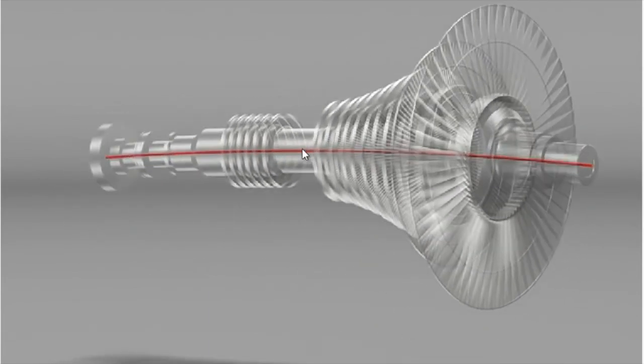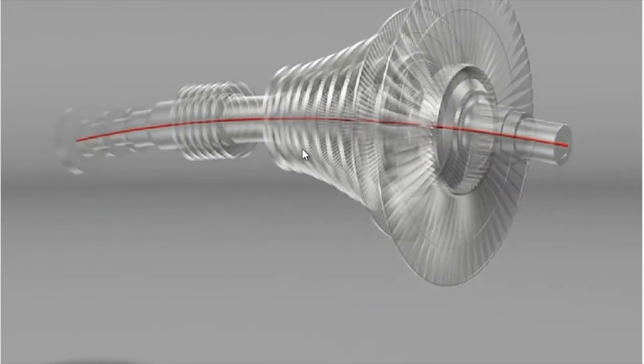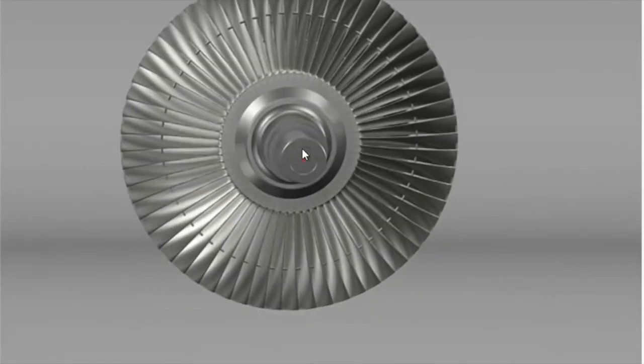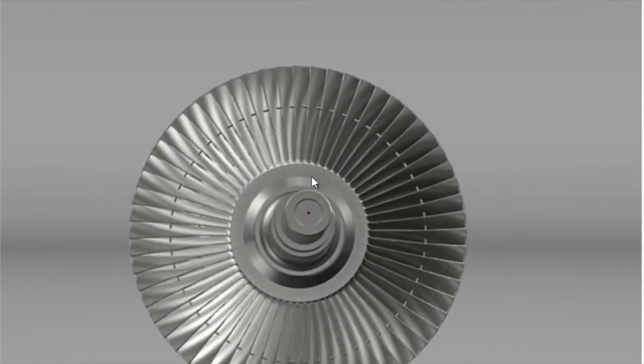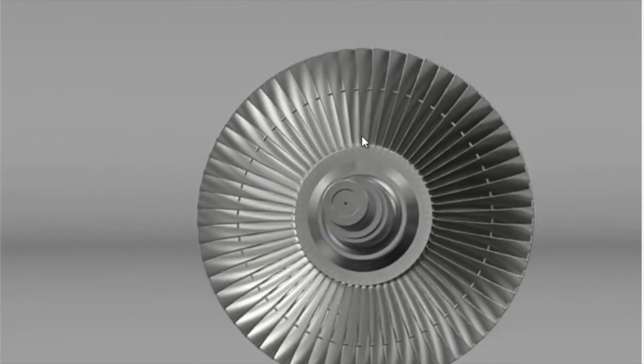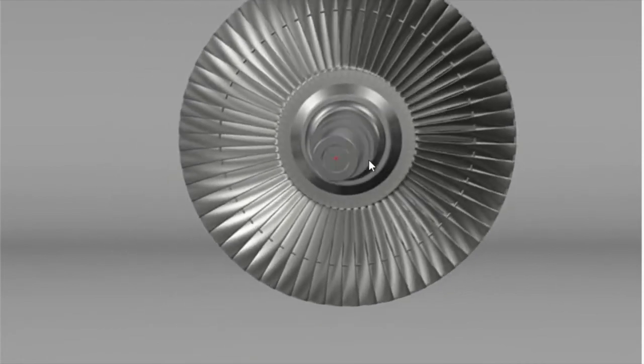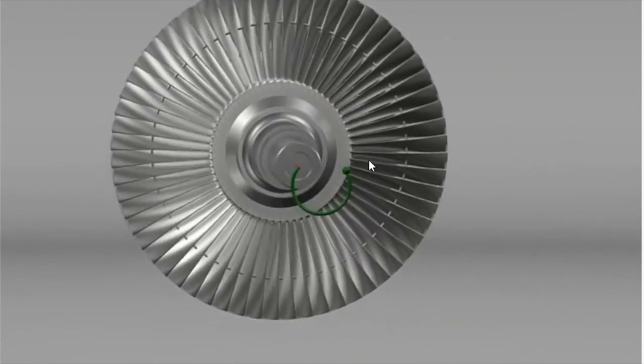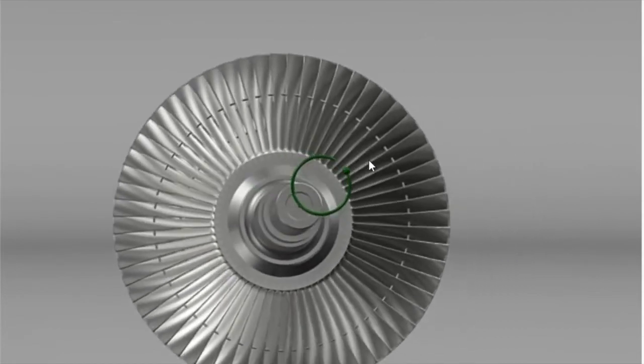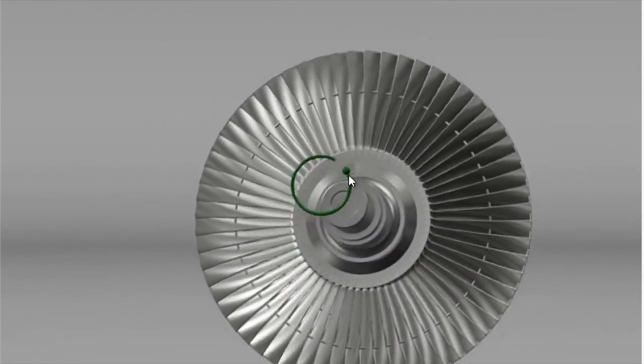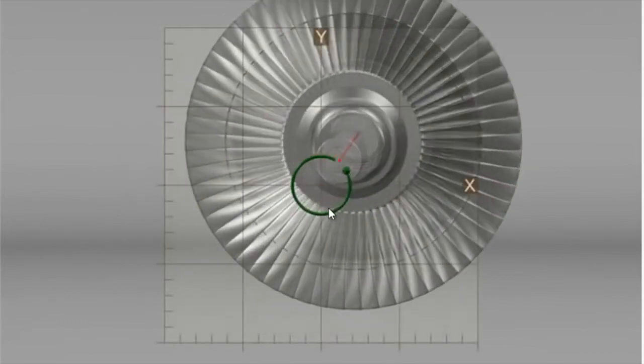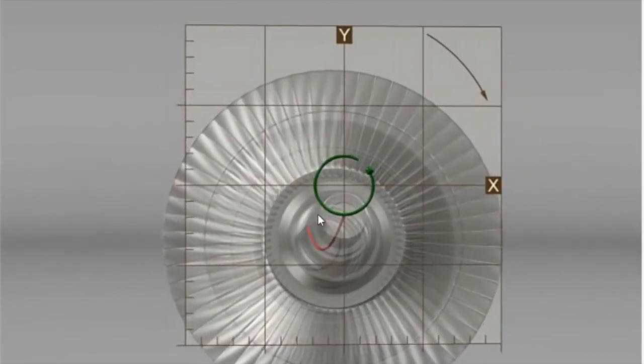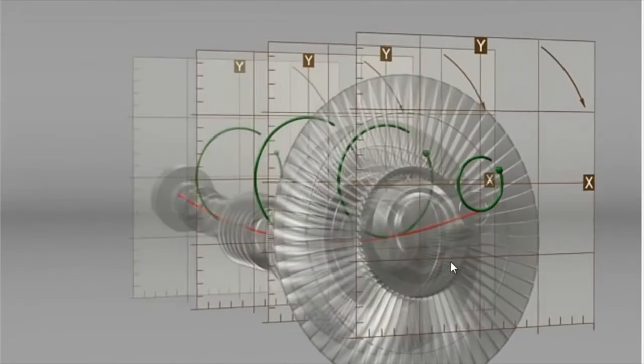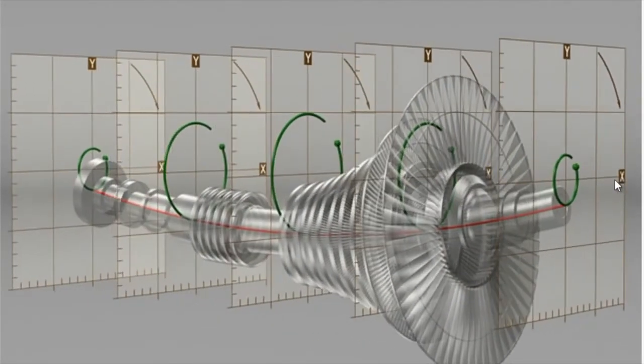A lot of detail we could go into, but I'd be interested in how do I take measurements to tell that's what is going on. Well, imagine if we had our two proximity probes at 90 degrees apart, taking the measurements, and we compared the two sine waves, we end up with a Lissajous figure, as it's often called, or an orbit. We plot the two sine waves against each other, we end up with a circle, if it is moving in a circular motion. And we plot that on a graph, as you can see here, Y being the top, X being the side.